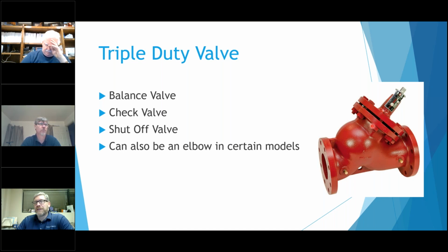I know a lot of people on these systems these days don't want to put balance valves or triple duty valves in, and you're running the pump off of a VFD. And that's okay. It's not typically a problem. However, if the head was overestimated and that pump starts to run on the end of the curve, where it's falling off the curve, the VFD is not going to magically pull it back onto the curve. You actually have to add some type of pressure drop to the system. On some of these retrofits where they're pulling these out, you can find out, well, I'm off the curve. I've got to slow it all the way down to where I'm not providing heat, but the pump sounds good. But if they had a triple duty valve or a balance valve, they can actually close this down on this stem and add the pressure drop so they can get back on the curve. I'll highlight a little bit of that when I'm talking about the variable speed curves and what have you in a little bit.